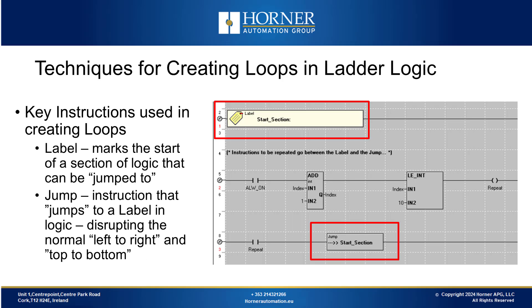Now let's look at some key instructions needed when creating both for and while loops. First, we will look at the label instruction, which can be seen at the top of this ladder screenshot. Labels can be used to label sections of your logic or to mark a section in your program you want to be able to jump forward and back to. We also have the jump instruction, highlighted in the bottom of our screenshot. When executed, the jump instruction causes the program to jump either forward or backward to a specific label. In our screenshot, we are jumping backwards.